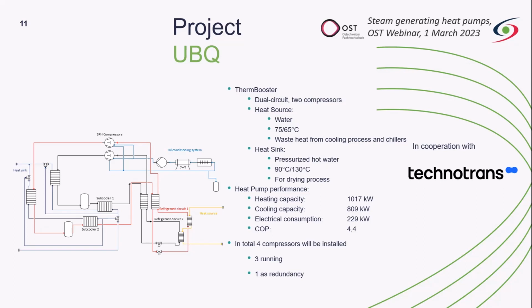On the slide before, I showed that they need 1.5 megawatts. So this is one of the ways how we can build in redundancy here. Means even if one compressor fails or we need to service one compressor, the rest of the compressors can continue to run because the refrigerant circuits are separated from each other. On the heat source side, nevertheless, we go first through the first evaporator and then through the second evaporator. This reduces the temperature lift from the first refrigerant circuit and therefore increases the efficiency slightly. So here we get water at 75 degrees and cool it to 65 degrees.